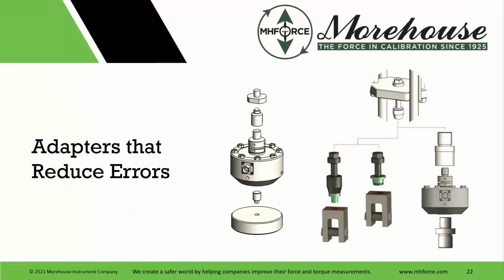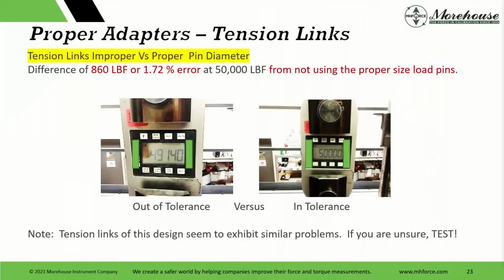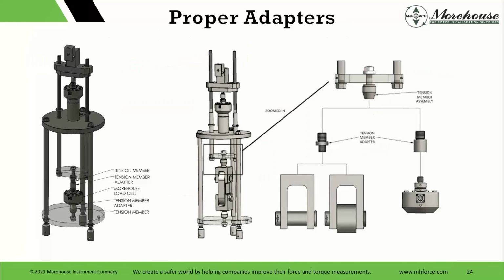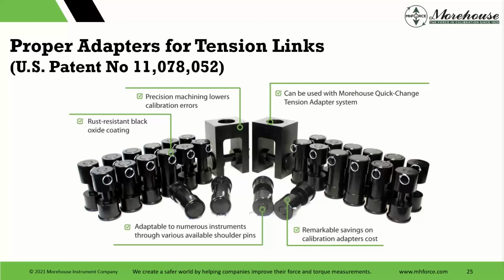So we start talking about adapters that can reduce some of these errors, and people have seen this one numerous times. But I'm also going to talk about safety on tension links this time through. But here, the right pin versus wrong pin, a difference of 860 pounds or 1.72% error on a device that's spec'd at 0.1%, or plus or minus 50 pounds. You put the proper adapters in here, proper pin size, everything else, you get a much, much safer measurement.